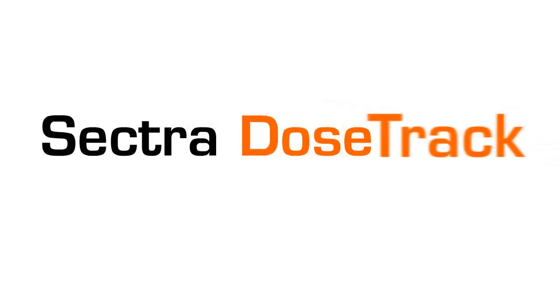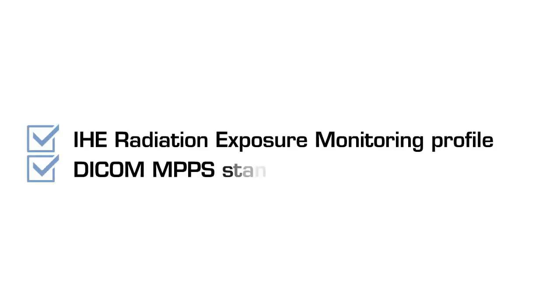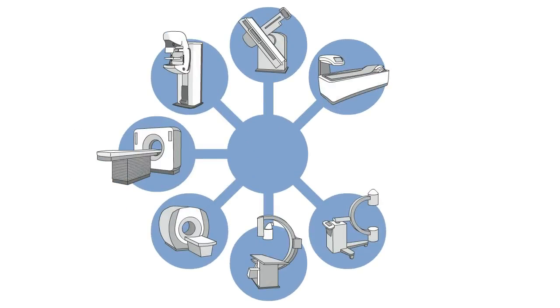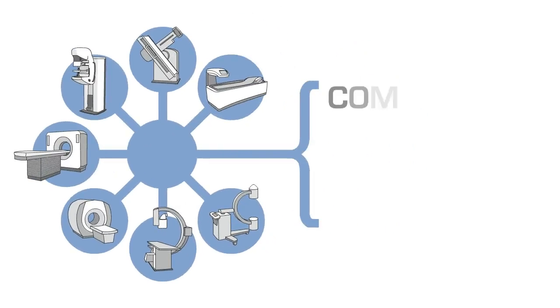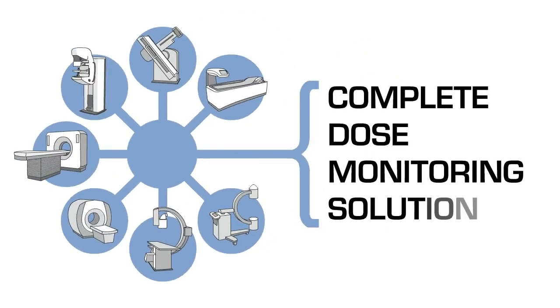Sectra DoseTrack supports both the IHE radiation exposure monitoring profile and the DICOM MPPS standard, enabling the connection of almost any modality to gain a complete dose monitoring solution.